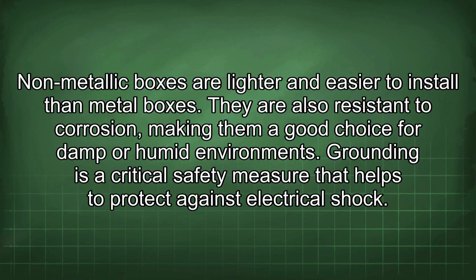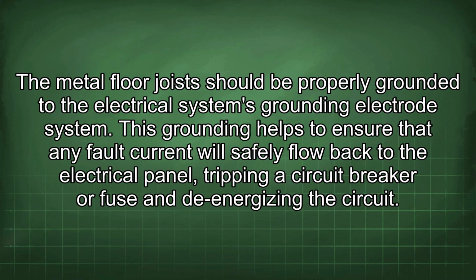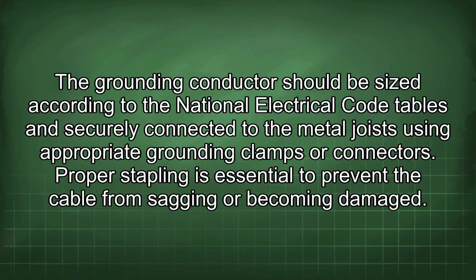Grounding is a critical safety measure that helps to protect against electrical shock. The metal floor joist should be properly grounded to the electrical system's grounding electrode system. This grounding helps to ensure that any fault current will safely flow back to the electrical panel, tripping a circuit breaker or fuse and de-energizing the circuit. The grounding conductor should be sized according to the National Electrical Code tables and securely connected to the metal joists using appropriate grounding clamps or connectors.